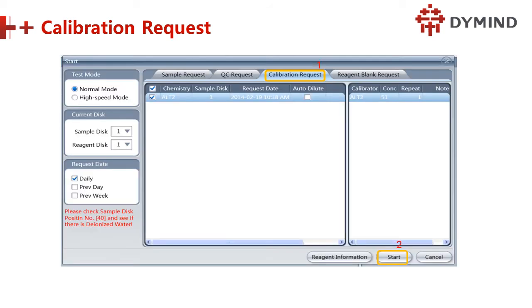So next is calibration request. Click chemistry and start it. This is the normal mode and the high speed mode. But generally, normal mode is better. Okay, don't change that. And the daily, or per week. This one we use daily, right? Daily control, daily calibration.